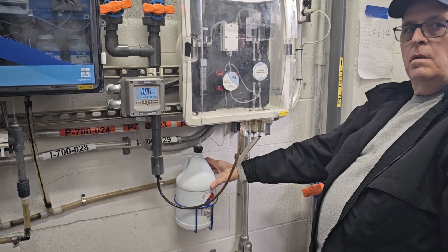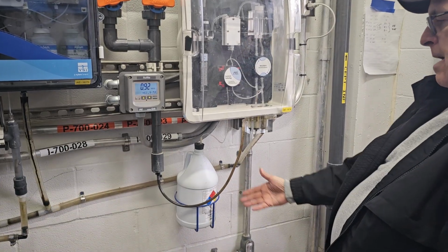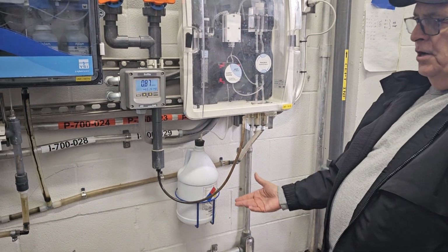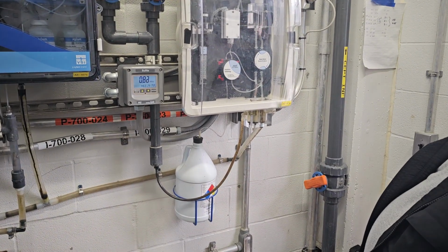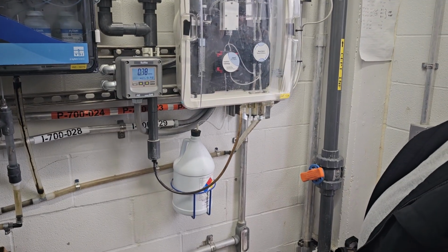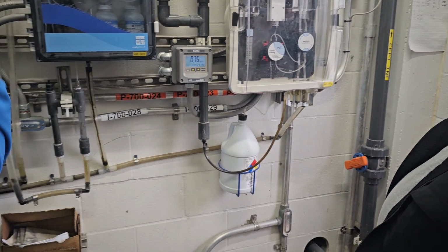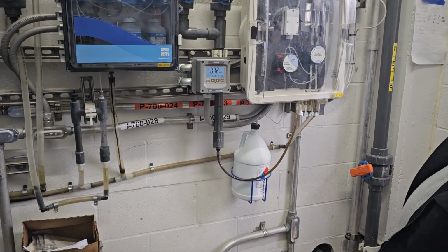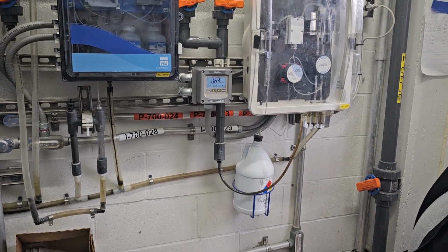How often do we have to swap out that reagent? I wouldn't think very often, it's a gallon jug, basically sulfuric, so that's not going to go bad. Go to the reagents for the chlorine analyzer, those have a very short shelf life.